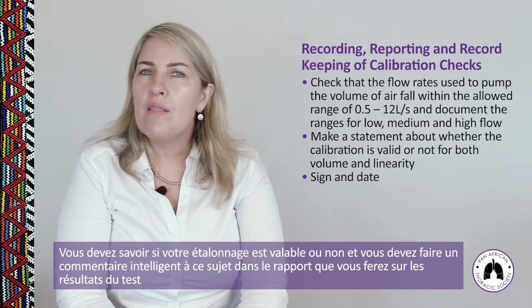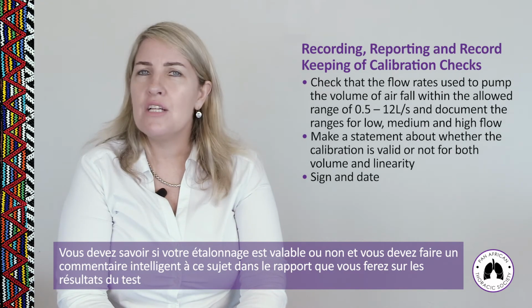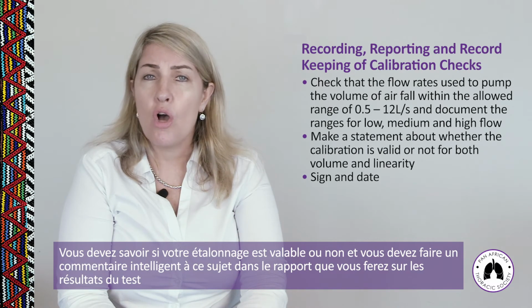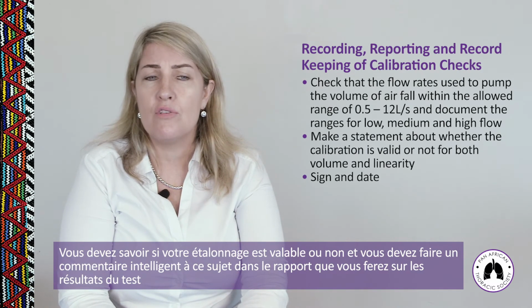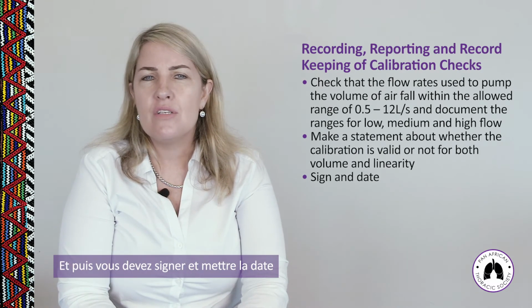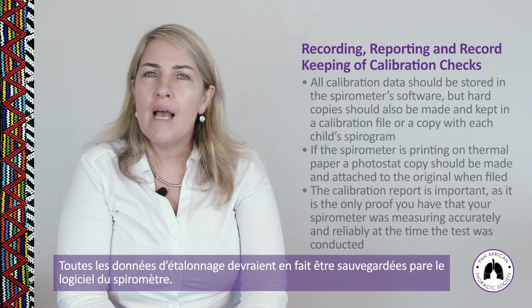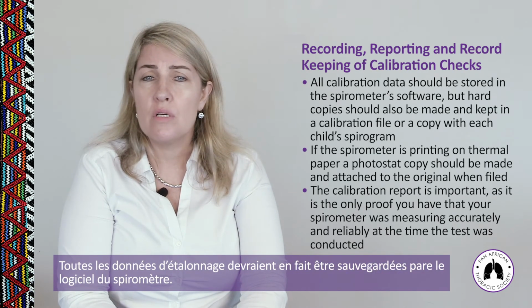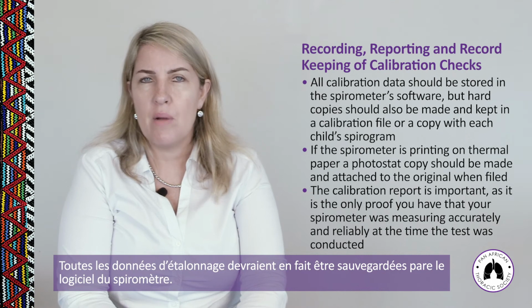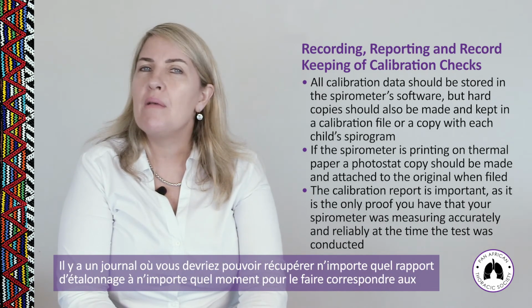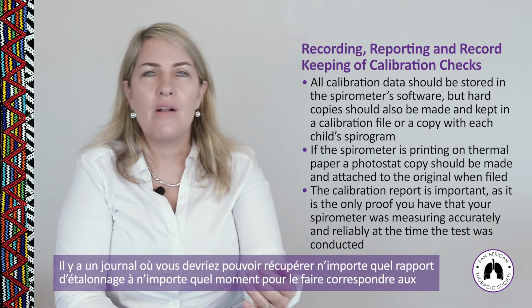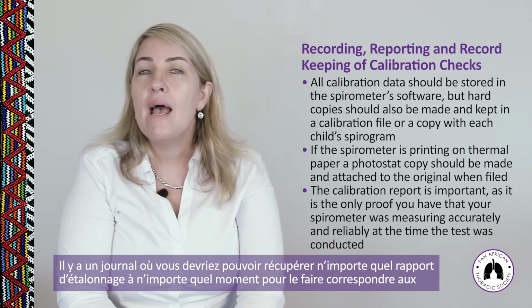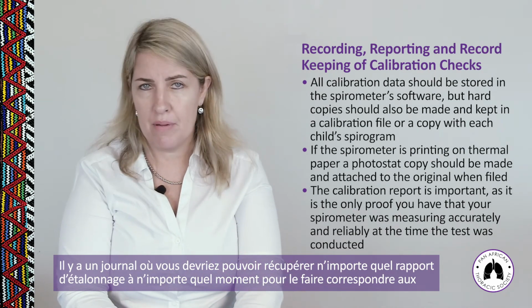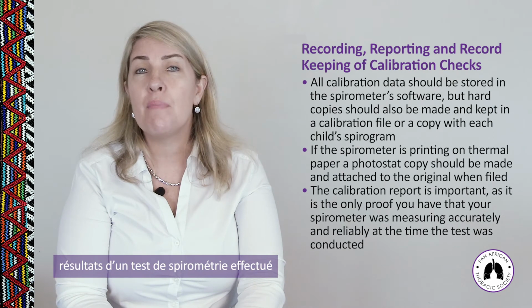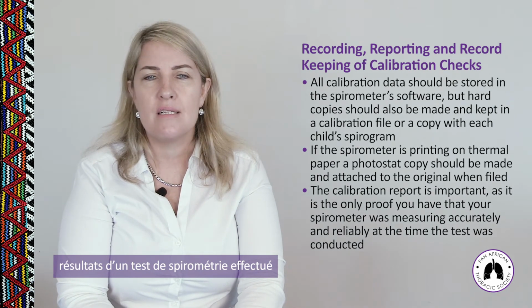You need to know whether or not your calibration is valid and to make an intelligent statement on that when you report on your test result itself. And then you need to sign and date. So all calibration data should be stored in the spirometry software. There is a log where you should be able to go back in the software and pick out any calibration report at any time to match it up to a relevant spirometry test that you might have conducted.